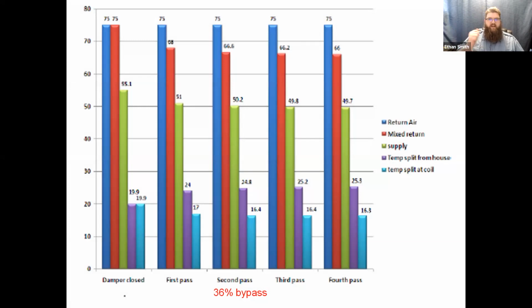The colder air you bring into that coil, the less it's able to absorb in terms of heat from the house. Once we start to see these discharge air temperatures drop along with it, we start worrying about maybe causing an issue with freezing in the future. This particular system, a 36% bypass, is the maximum that it will still operate under. When I ran the numbers for this system, a 3-ton AC, I can't remember what my percentage of bypass was, but there you go.